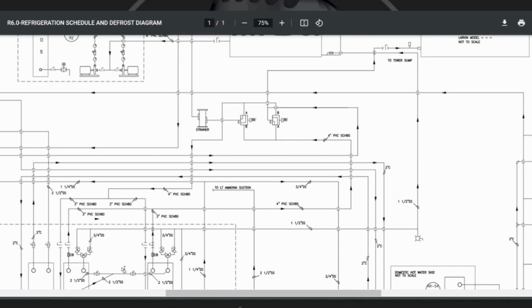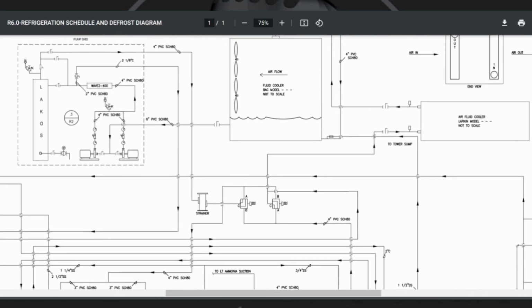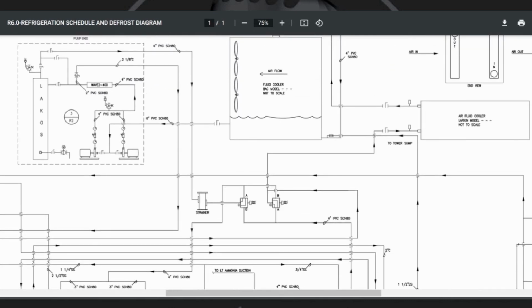But we reverse them once a week just in case any particles get through the separator and get on the entering edge of a plate heat exchanger. I'm sure you've looked inside plate heat exchangers. The spacing between the plates is less than 1/8 of an inch, so it's pretty tight. So any particles that might lodge in there, we blow out, blow back into the LAKOS to be separated. And that's what this motorized, it looks like a motorized ball valve here at the bottom. That's basically your blowdown for that, correct?